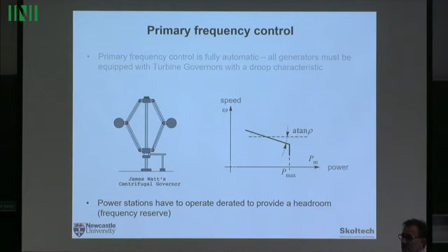So what happens in primary frequency control? This is frequency versus time. Here we suddenly lose sizable generation, so frequency starts to drop. The initial slope of decline is determined by system inertia. If nothing happened, that line would go down to zero and everything would grind to a halt. But as frequency starts to drop, turbine governors open up and provide more power, so the slope changes, and you get a point of inflection as more power comes in.